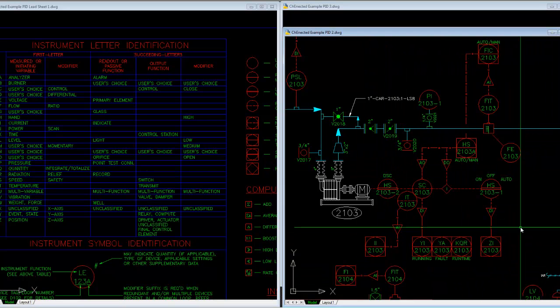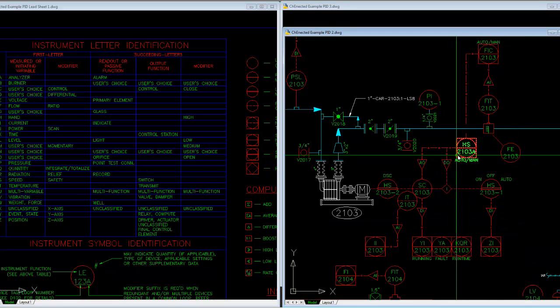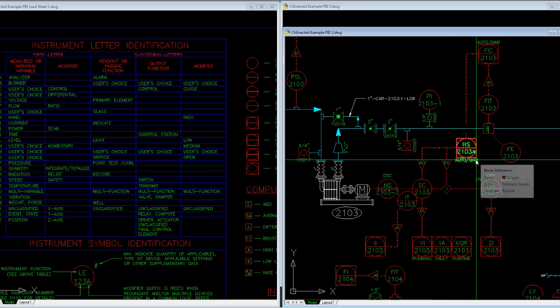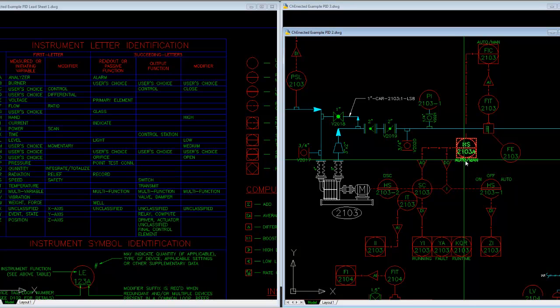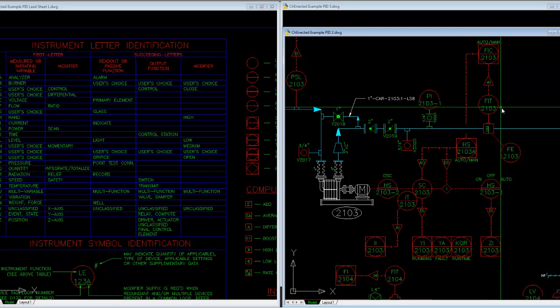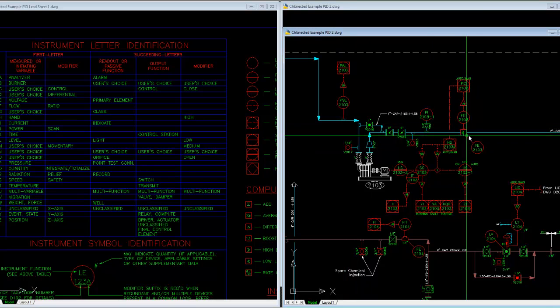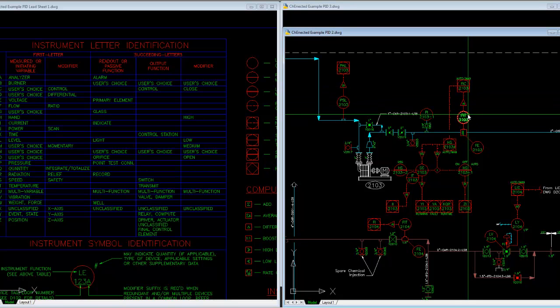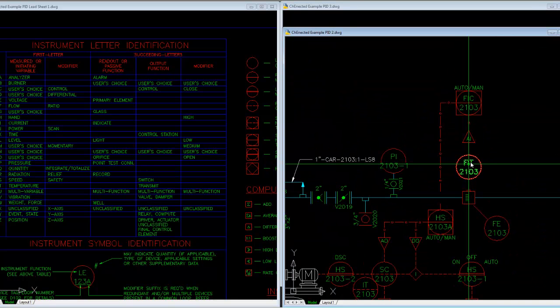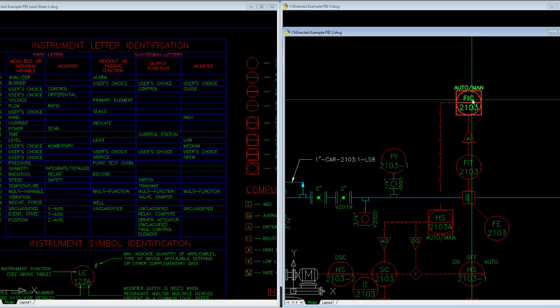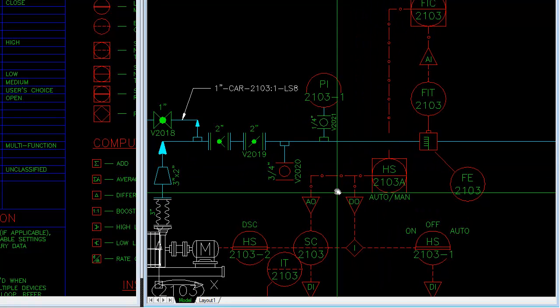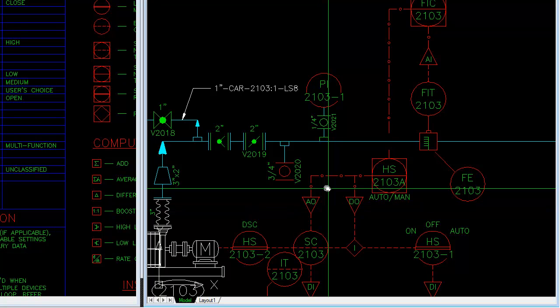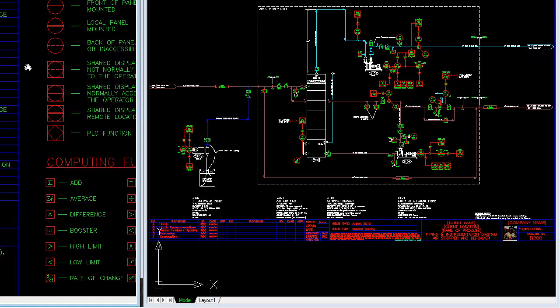Looking at how you interpret the functionality of a system: the hand switch available to the operator on the HMI kind of emulates the field switch. When the field switch is in auto, the operator has the ability to start and stop the blower or place it in auto. When it's in auto, a flow indicating transmitter provides a reading of how much vapor is flowing in that line. There's a desired set point for flow, and the reading from the flow meter comes into the system through a flow indicating controller you can interface with on screen. When in auto, it sends an output to ramp and adjust the speed of the motor — that's an example of interfacing with control systems as illustrated by squares around circles.